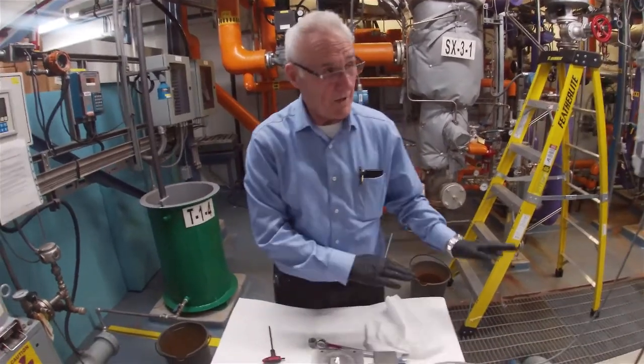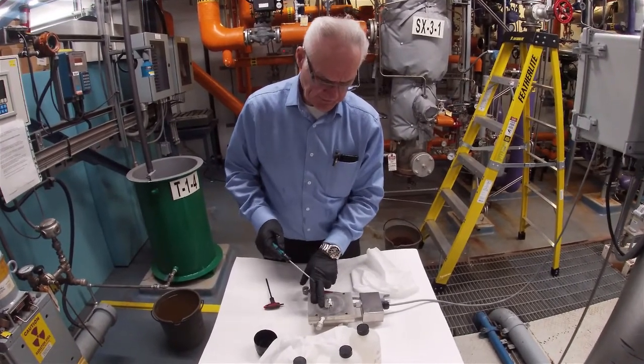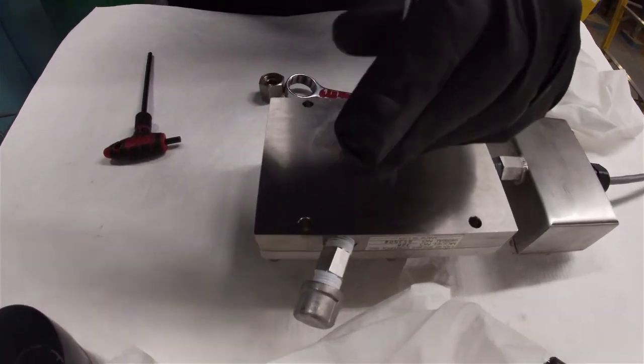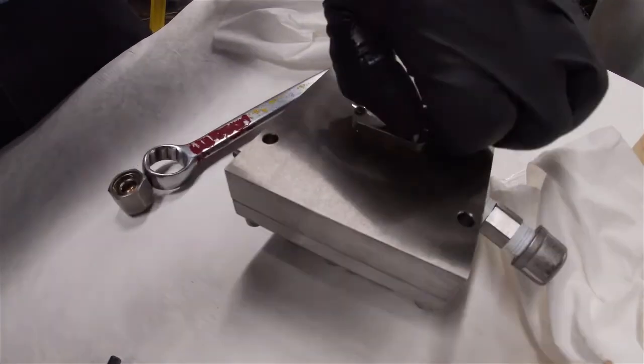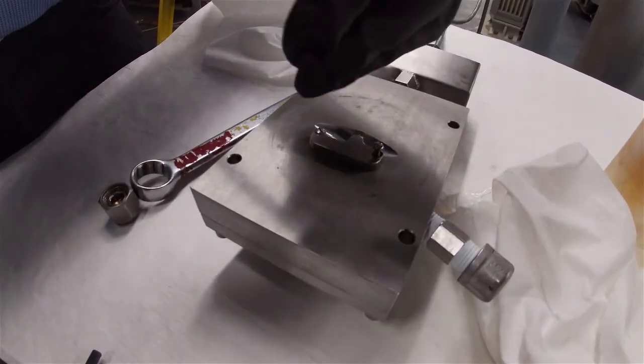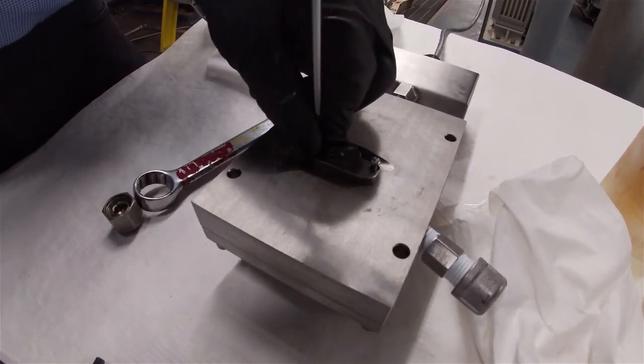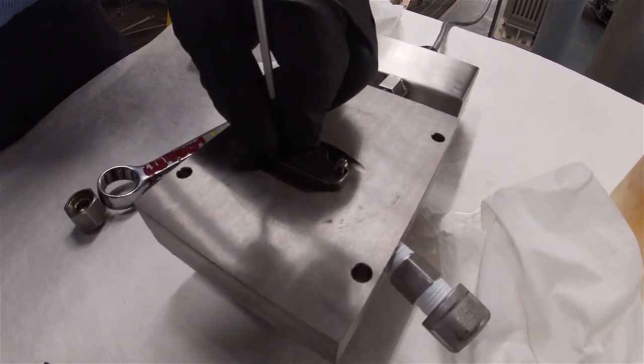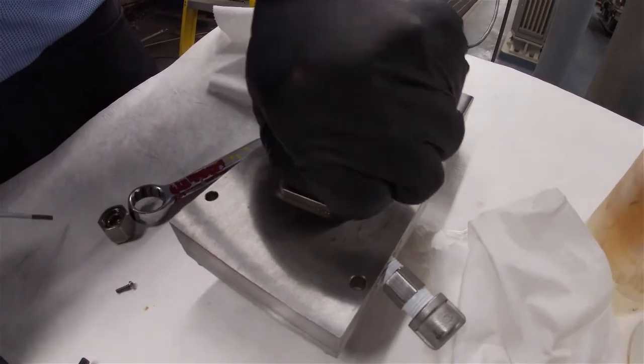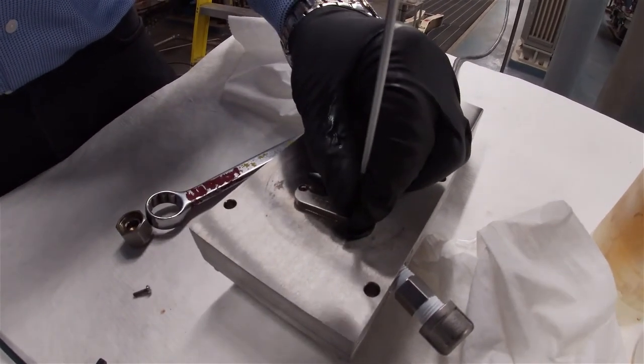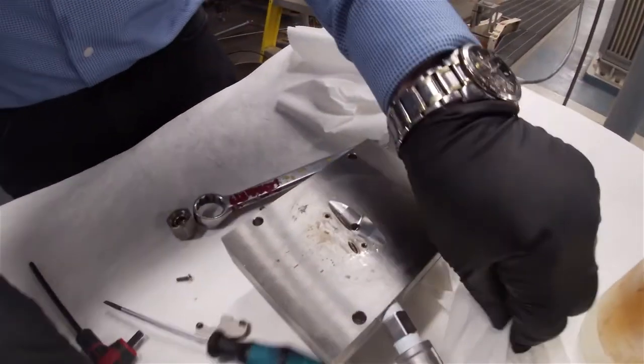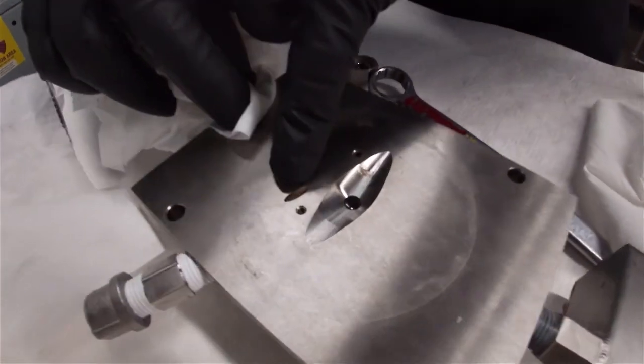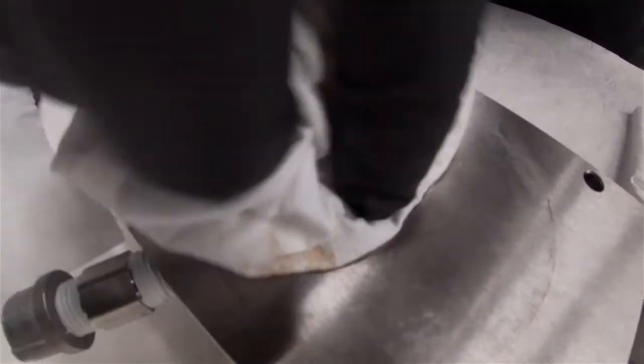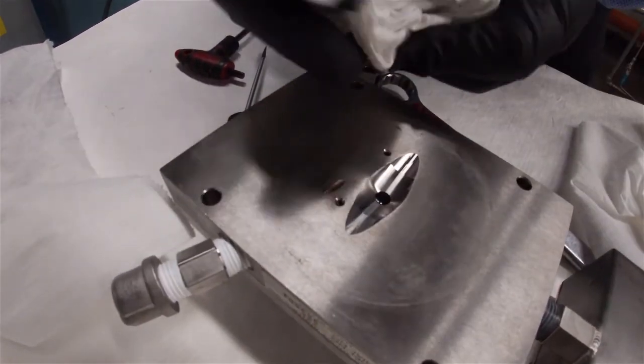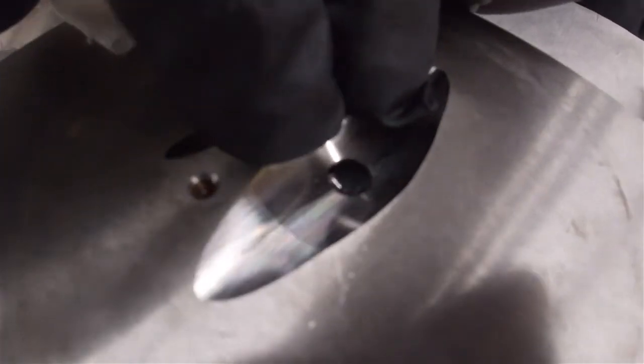Okay, now we've got the unit off on a bench, turned upside down. First thing we've got to do is remove the jet wash nozzle. So I'm going to take that off here. Wipe it down. You can see the hole right there where the jet wash would be coming in through this pipe. We don't use the jet wash because we're not dealing with black liquor. The ethylene glycol doesn't really leave a film on the prism itself. And down in the very bottom, where my fingers are pointing, is the actual prism itself.